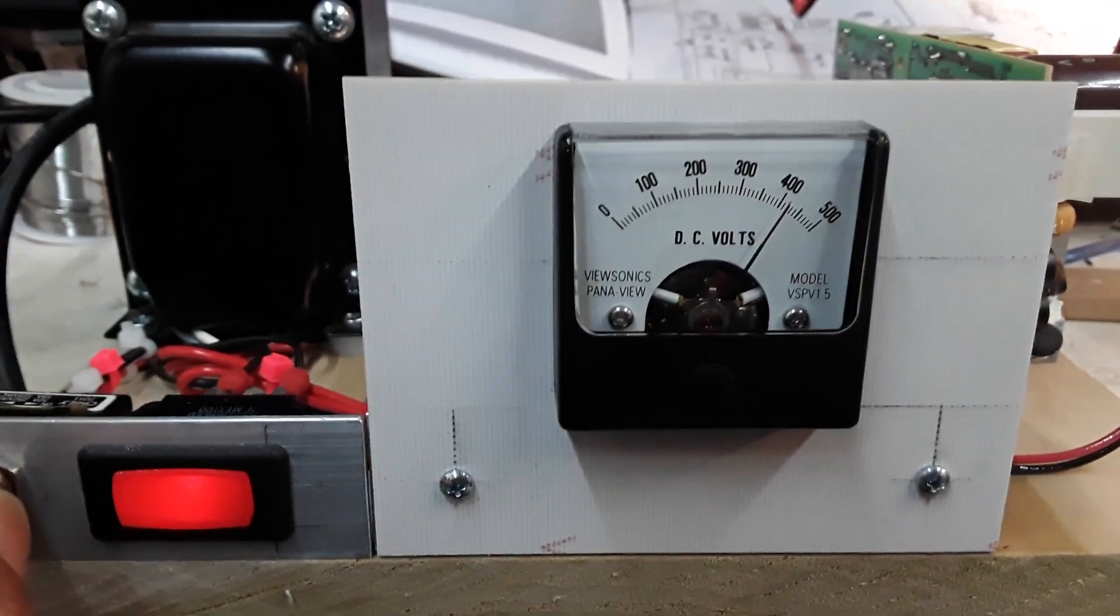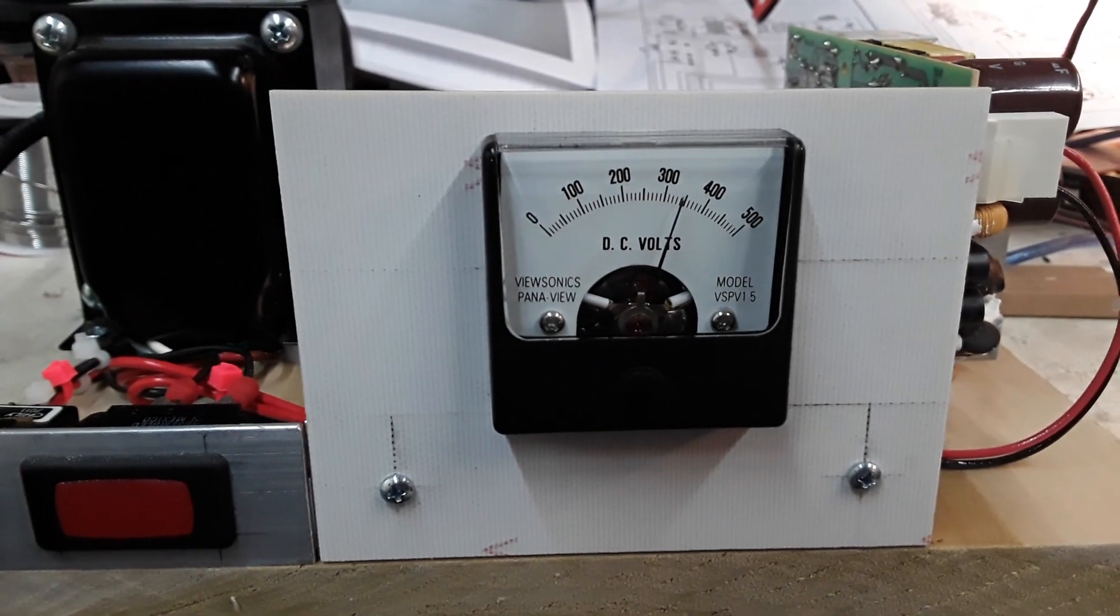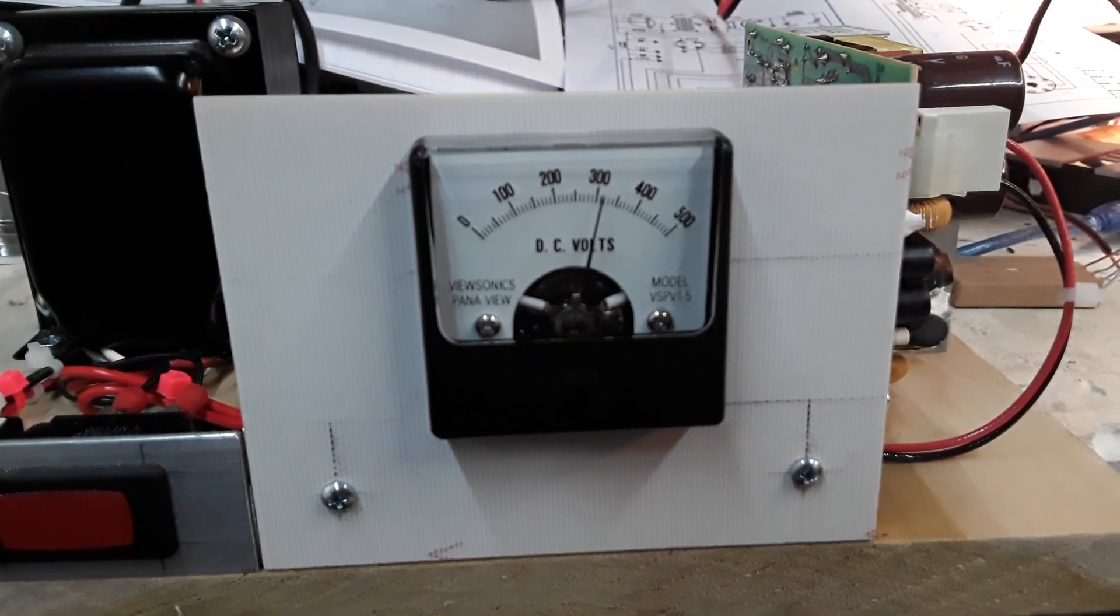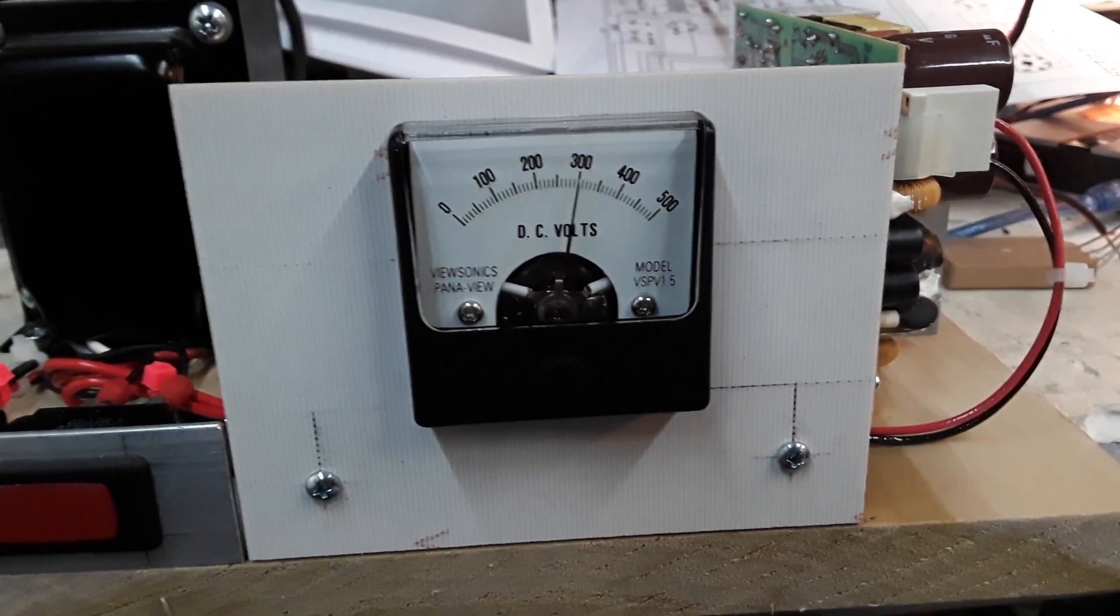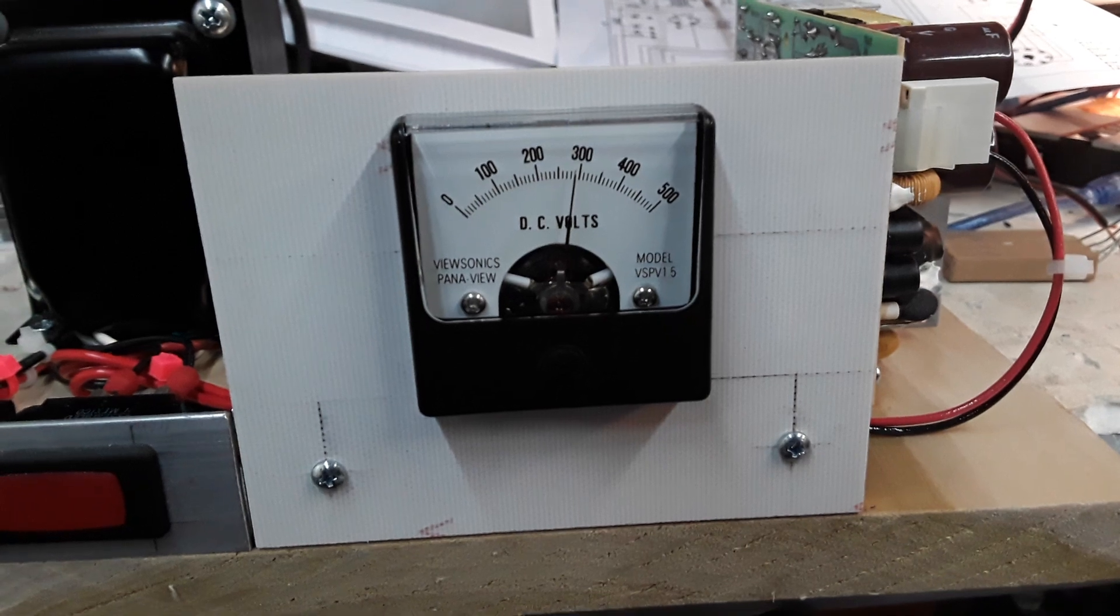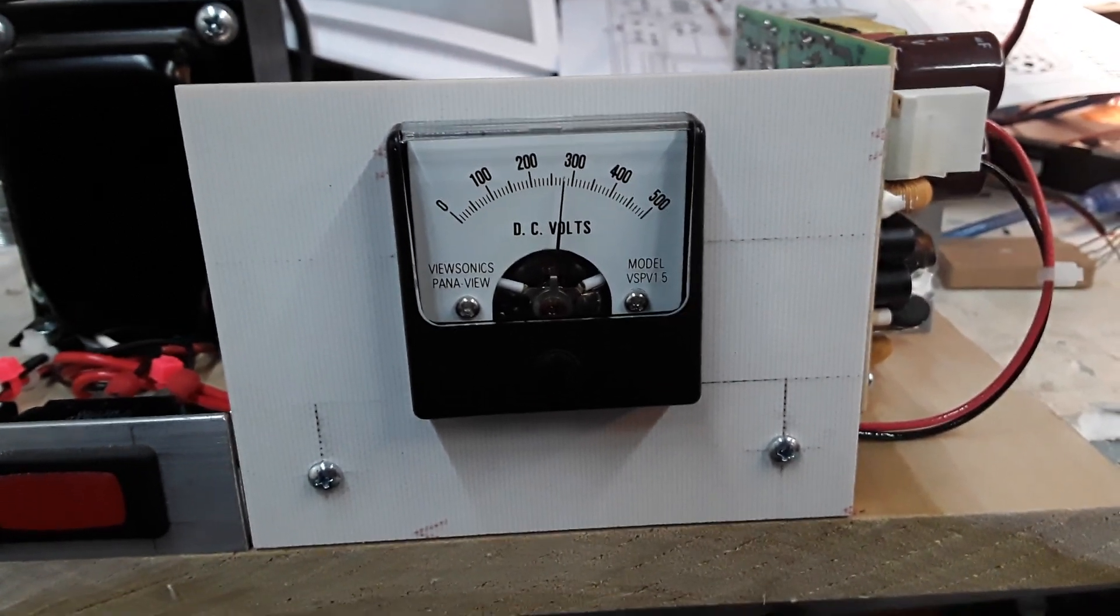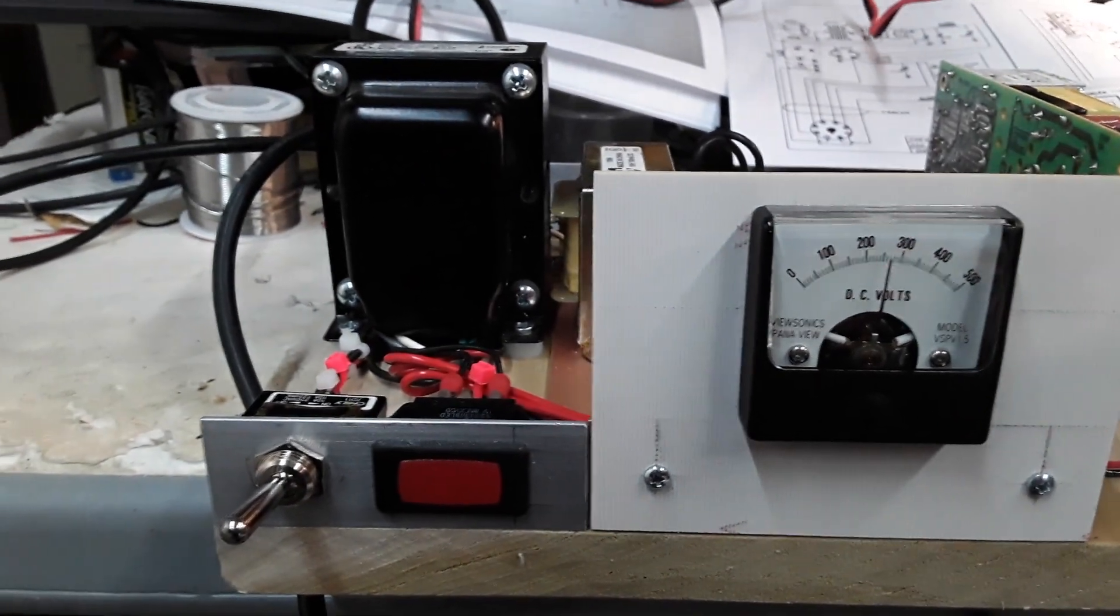So we're going to shut that off, and look at that. There's hardly any bleed on that circuit. Look how long it takes for the voltage to go down a significant amount. So you never want to put your hand in there, and that's why there's the importance of bleeder resistors in these circuits to make sure that the devices are bled down thoroughly.